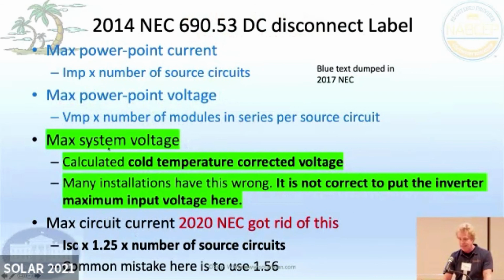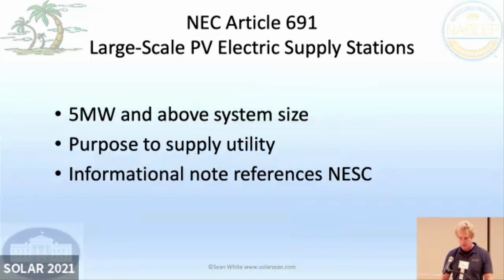This is for the DC disconnect. Oftentimes it's just on the inverter, so there's less stuff. And if you went to the 2014 NEC, you had to have your operating current, your operating voltage, your maximum voltage, and your maximum current. This requirement is actually getting to be less stickers. A lot of people make fun of the sticker quota you have for all these things. Like, did you meet your sticker quota? Less stickers. And then we did talk a little bit about 691, large scale PV.